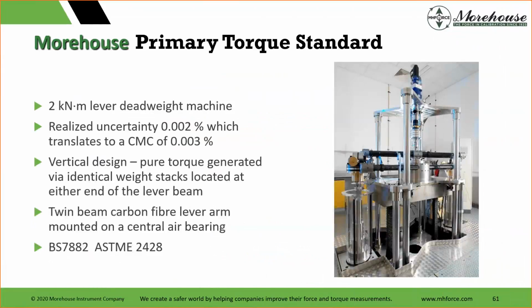And now we're kind of wrapping up. I'm going to talk about our standard a little bit more for those that have been talking about it. Here's what it is. Look at that. It's carbon fiber arms. It's a 2 kilonewton meter lever deadweight machine. Realized uncertainty of 0.002, which translates to a CMC of 0.003. We said 0.0025 a lot of times. That's the accreditation requirement. And when we start looking at calibration process uncertainty, when we involve all the technicians and everybody else, it raises it a hair.